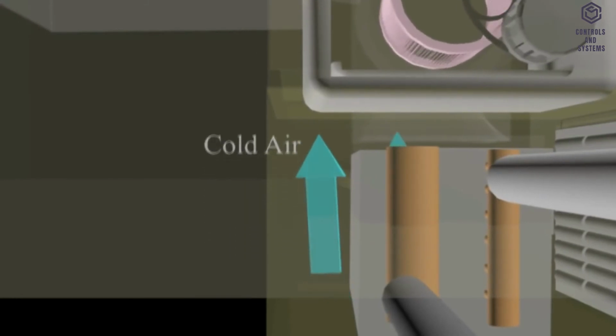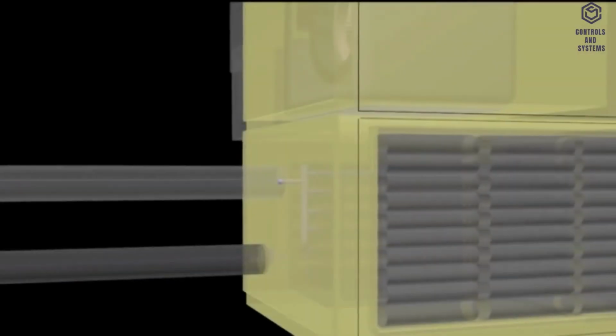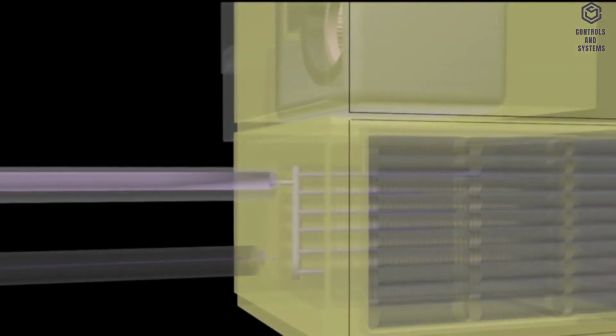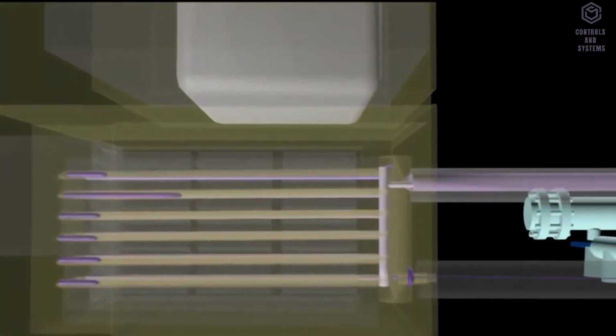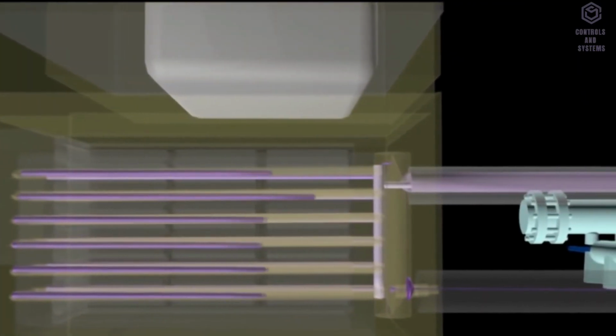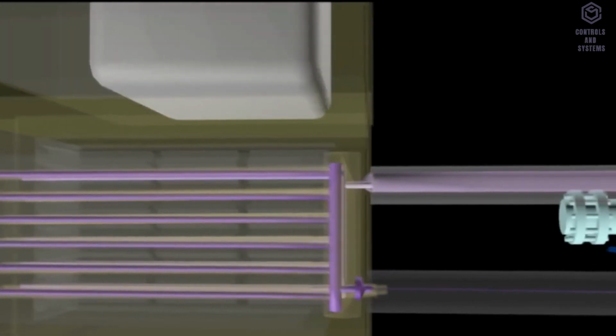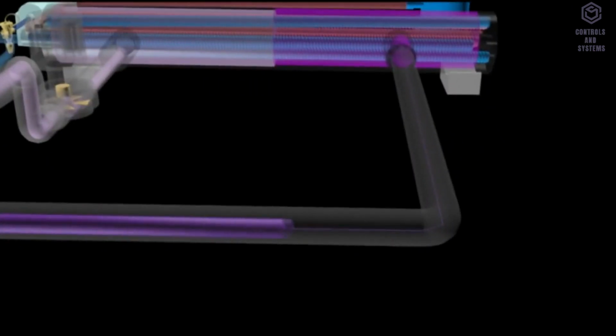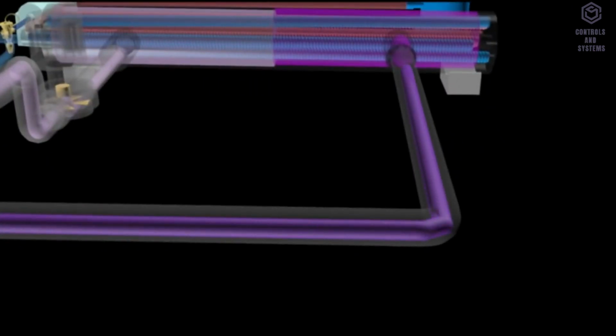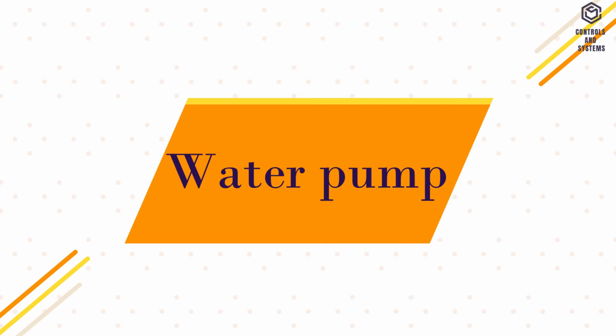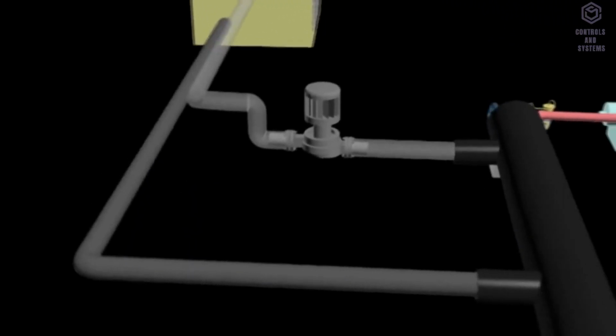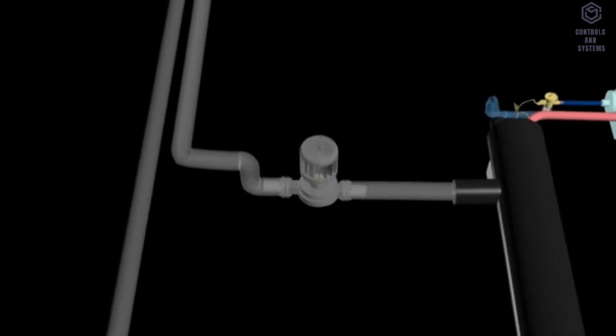Cooling coils commonly used in the system are the tube and fin type. After absorbing the heat from the hot air, the chilled water is known as chilled water return. Normally chilled water return is marked with light blue color. Chilled water return will return back to the chiller to transfer the heat to the refrigerant in the evaporator. Water pump. This cycle will continue as long as the pump is functioning well.